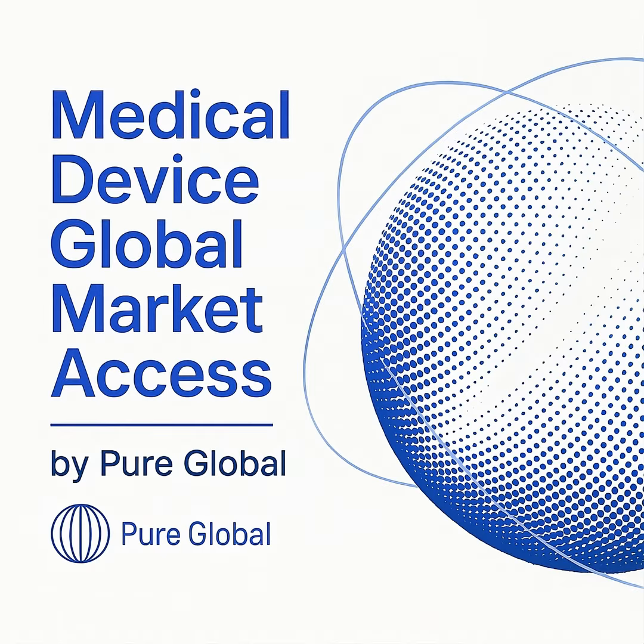The HSA employs a four-tier risk-based classification system, labeling devices from Class A for the lowest risk to Class D for the highest risk. This structure is not unique to Singapore. It is harmonized with the principles set forth by the Global Harmonization Task Force, known as the GHTF, which has since been succeeded by the International Medical Device Regulators Forum, or IMDRF.